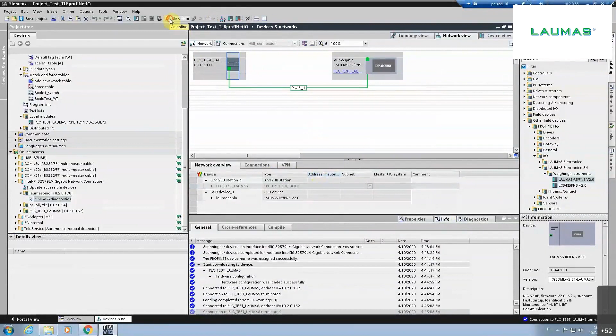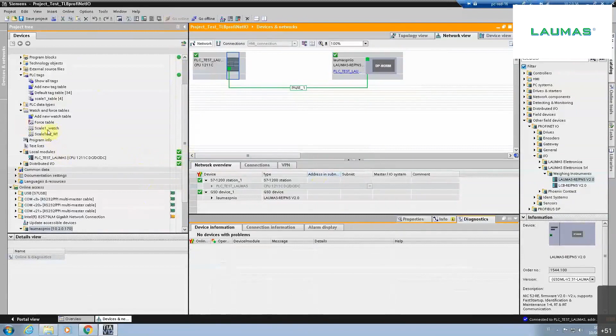Okay, all the green symbols mean that all the items on our Profinet network are working correctly. Now we can access our scale test watch table, and enabling the monitoring function, we are able to see all the data currently exchanged between the PLC and the instrument. Here we have the gross weight and the net weight values received, and the current value of the status register. If we go to our protocols manual and compare the current value of the status register with the table corresponding to this field, we are able to see that the current value means that the weight value is stable.